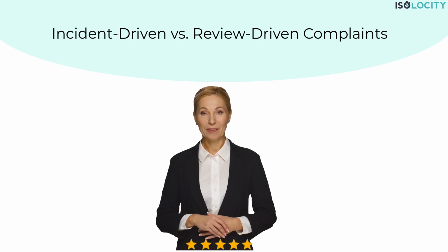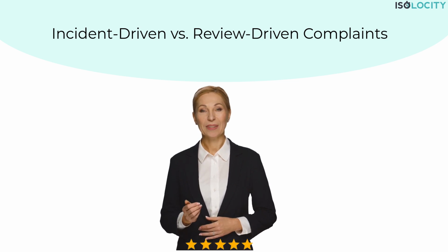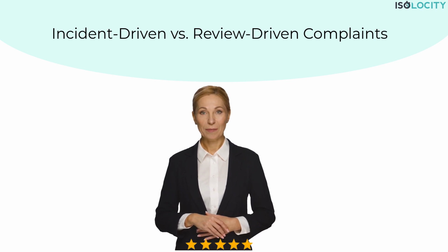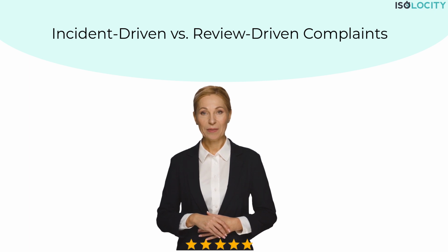Incident-driven complaints. These arise directly from an adverse event or product failure reported by a customer, healthcare provider, or regulatory body. These are often urgent and can have immediate safety implications. Review-driven complaints. These are identified during routine post-market surveillance, internal audits, or product reviews. They may not stem from a specific incident but rather from data trends that suggest a potential issue.